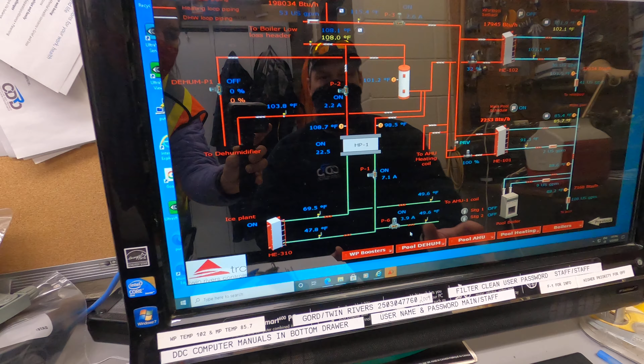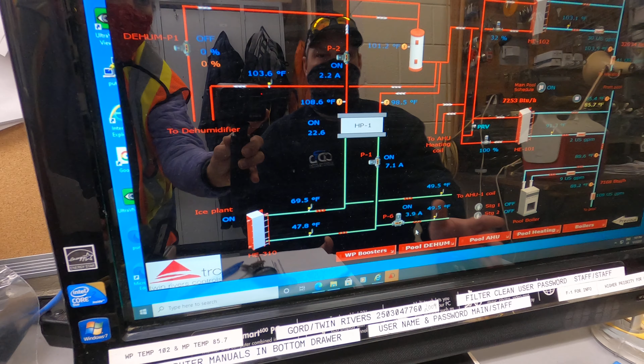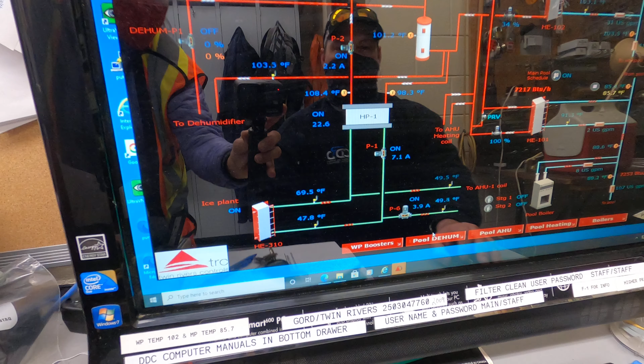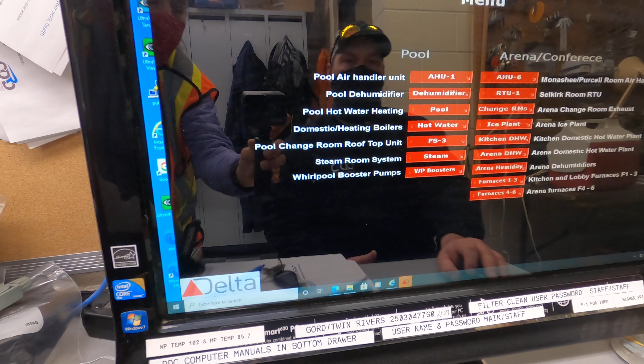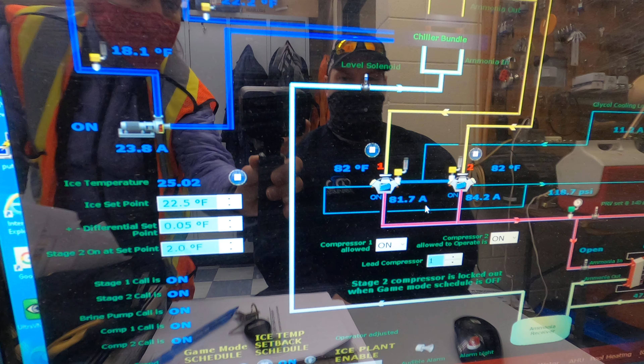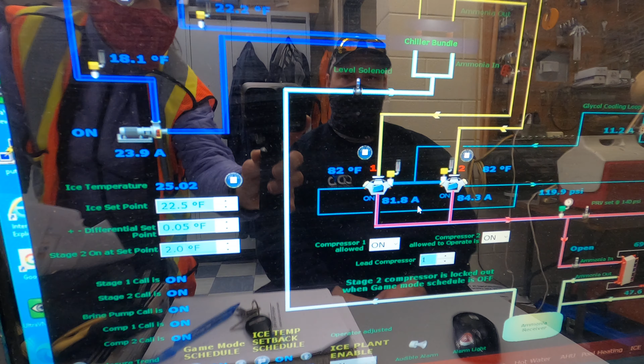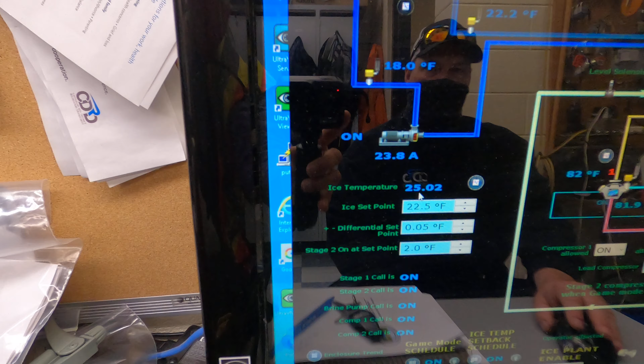In today's world, electricity is not cheap, so if you want to say, we're reducing our greenhouse gas emissions, but our cost of operation does rise with that. Let's go back here. Okay, now as far as our refrigeration plant goes, here's where I've got my compressors. Right now I've got two compressors running. It's showing me that they're both drawing 81 to 84 amps on my motors, and their heads are at about 82 degrees Fahrenheit. Over here you'll see that my ice temperature is currently 25 and I want to be at 22.5, so it's going to work for a while to get that temperature down.